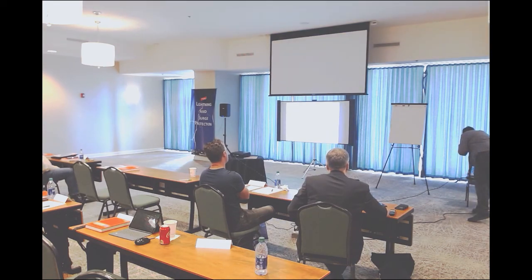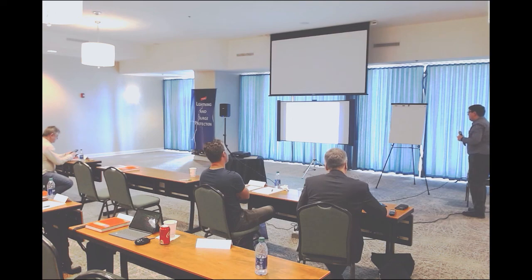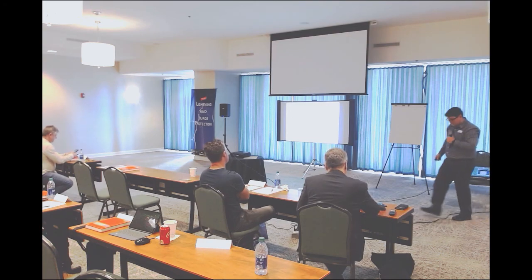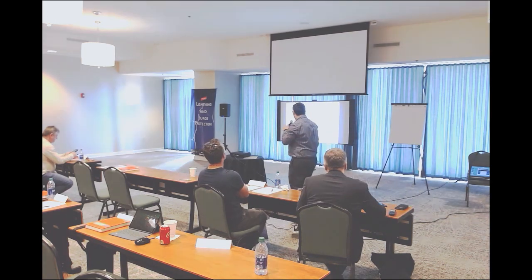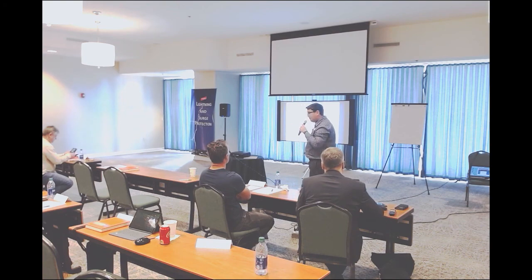So we saw this yesterday as well. A typical design example where you have a structure. And it's really easy, when you're on top of this roof, or on top of these tanks, to see that if I install a lightning rod on this end of the platform, I don't need to install anything in the region in the middle and only install something on the other side of the platform, because if I'm physically there or I'm taking this measurement in the 3D model, I can see that that distance will enable me to see that the sag of the rolling sphere would not touch that structure.